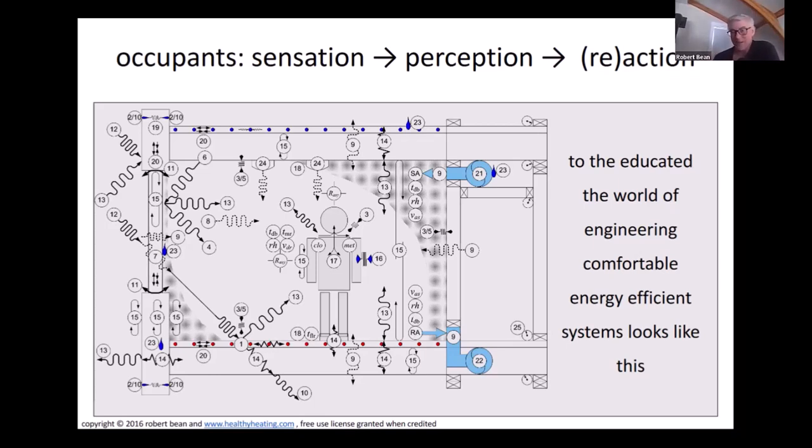They experience it with all of their environmental sensory systems, and in a very transient, ambiguous way, because of what happens to a building as the sun comes up in the morning. The building starts to get loaded with shortwave radiation from the sun. The solid surfaces absorb it, that's conducted through into the interior, and it's released as long wave radiation. Some of the shortwave radiation comes through the fenestration systems, depending on the solar heat gain coefficients and the shading that's there. That shortwave radiation now enters the space, and that contributes to discomfort. Some of it is absorbed by the interior surfaces and then converted to longwave radiation. So you've got shortwave radiation and longwave radiation.